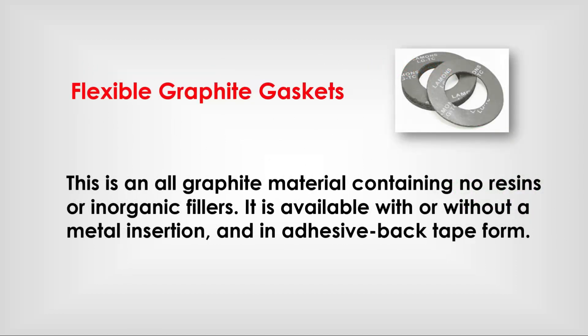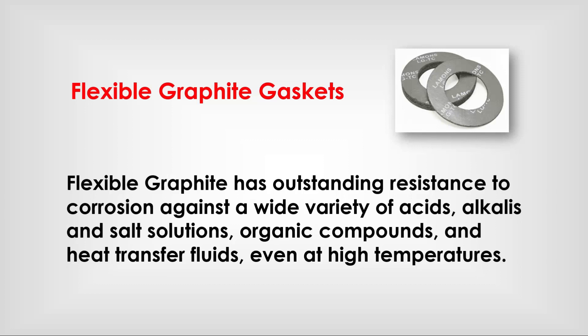Flexible graphite gasket: this is an all-graphite material containing no resins or inorganic fillers. It is available with or without a metal insertion and in adhesive-backed tape form. Flexible graphite has outstanding resistance to corrosion against a wide variety of acids, alkalis, salt solutions, organic compounds, and heat transfer fluids, even at high temperatures.